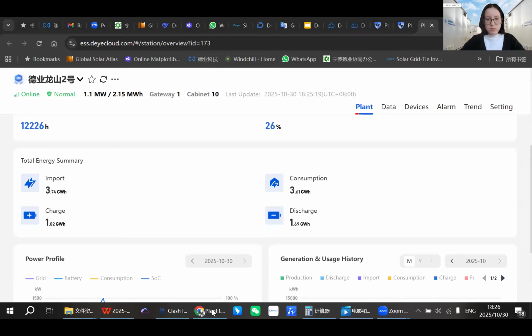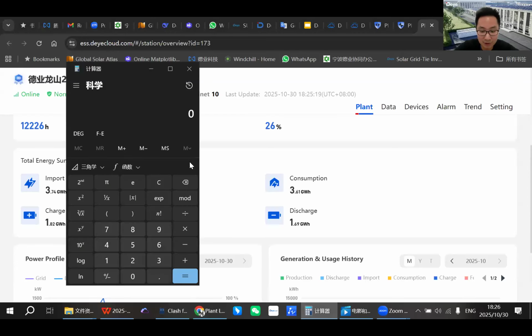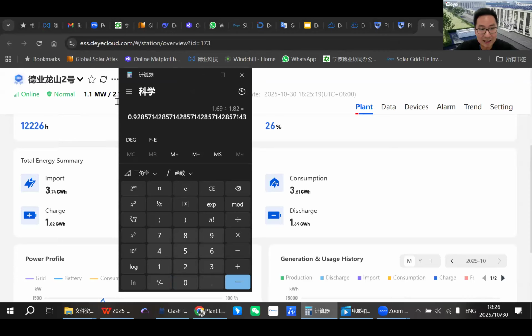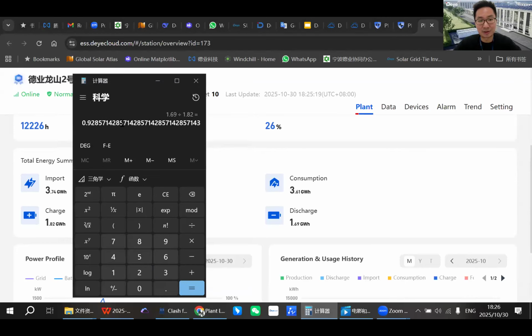Am I sharing screen? No, not yet. Okay, you started sharing, yes, it's visible now. So we have discharged 1.69 gigawatt hours by charging 1.82. So the actual efficiency is closer to 93%, even though we advertise it to be 88%. We like to be conservative in terms of performance. So on the spec sheet you will see 88% from us, but in reality, the sites that have been running for one year are telling us 92%.